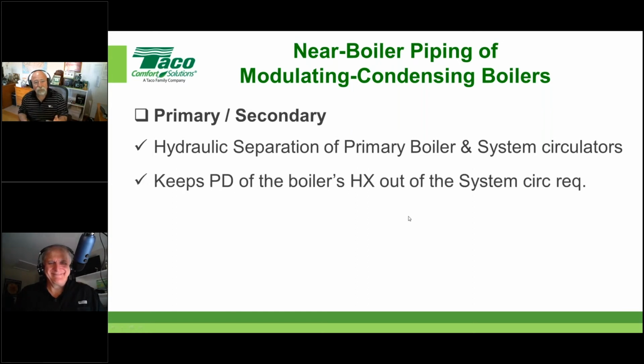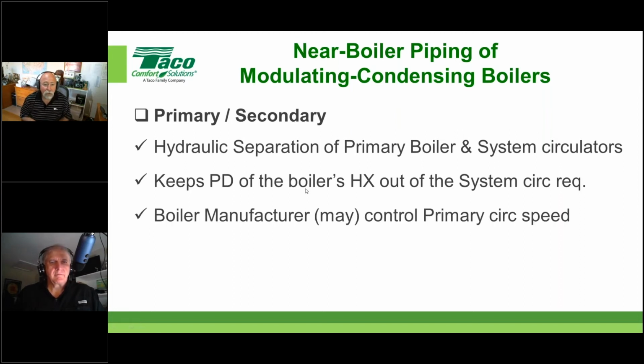The other thing is, in the days when heat exchangers only had very high loss coils in them, a primary secondary would afford the system circulator not having to overcome the pressure drop of the boiler's heat exchanger. Therefore, it could be sized more appropriately. So that's just another thing we get out of primary secondary.